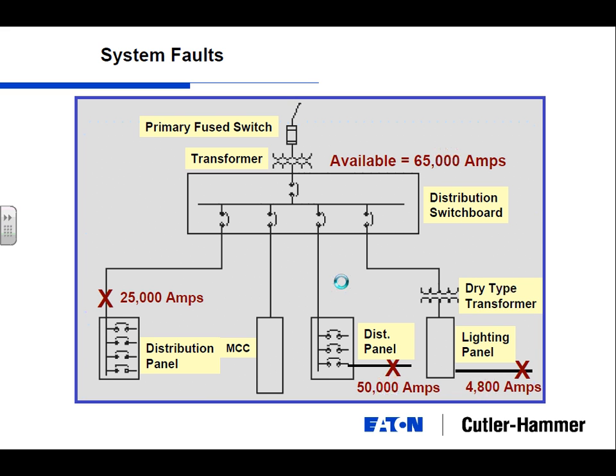Number one, it could be twice as far away, so you could have twice as much cable feeding. Number two, it could be a much smaller ampacity rating. So this distribution panel, maybe that panel is 1,200 amps. Maybe this distribution panel is only 200 amps. And why would that be a difference? Because at 1,200 amps, you get bigger cable. At 200 amps, you get smaller cable.